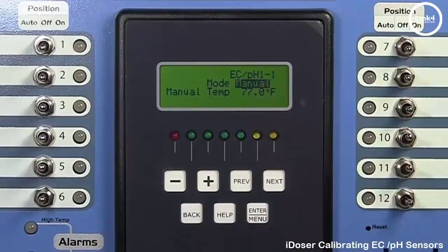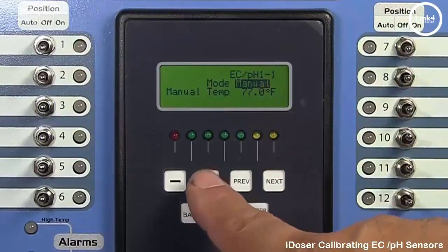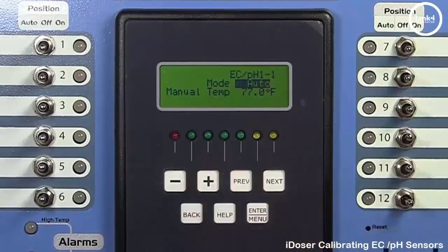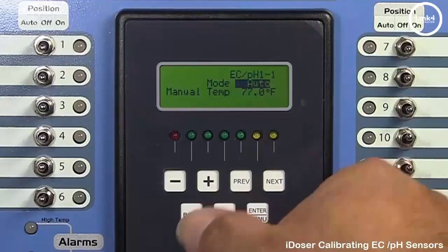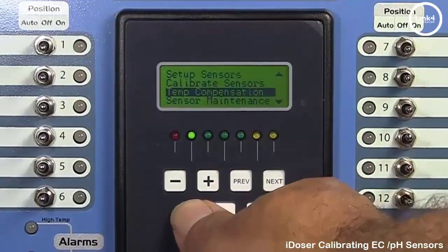Now the mode, we want to change it from manual to auto simply by hitting plus. Now the 77° Fahrenheit is no compensation whatsoever, and we recommend that you switch this mode to auto, and it will take and use the temp probe that is built into the EC probe. Now once you have done that, just simply hit back to get to the home screen.